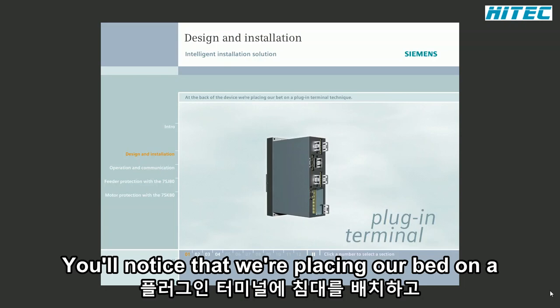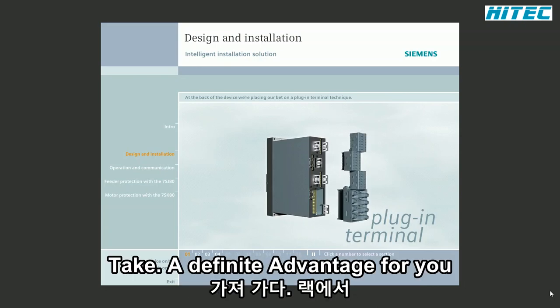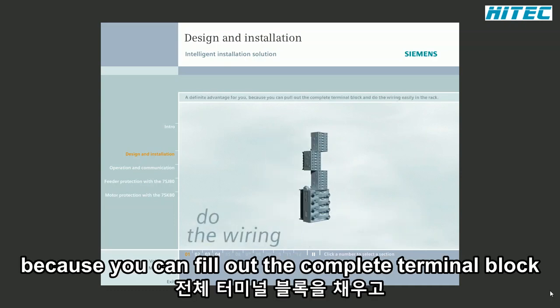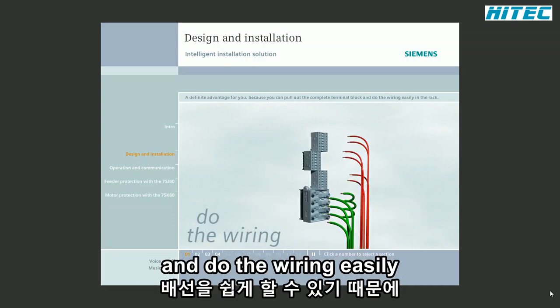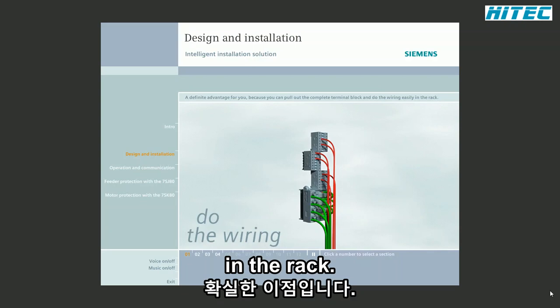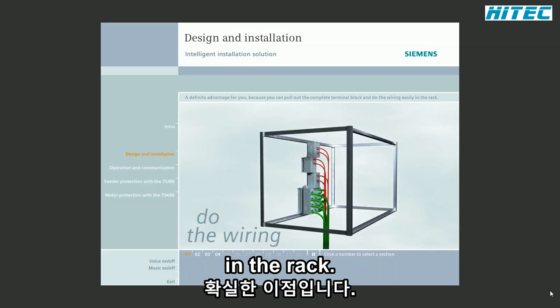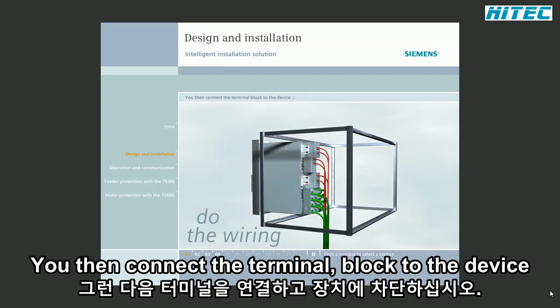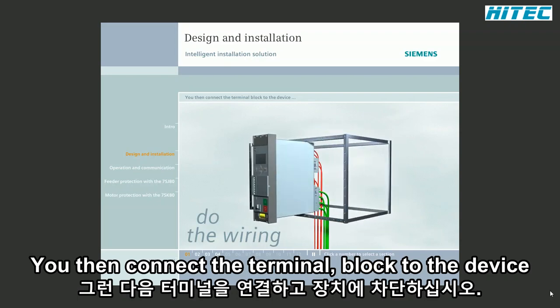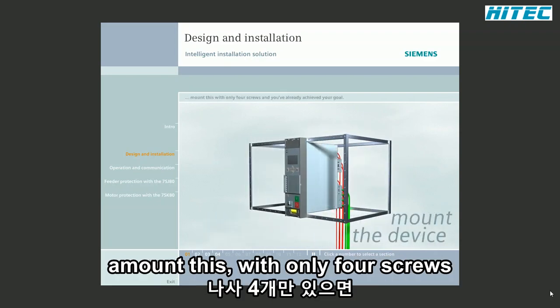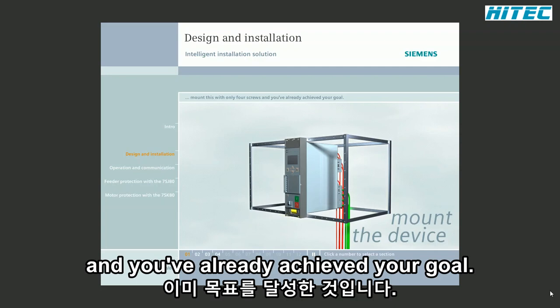You'll notice that we're placing our bet on a plug-in terminal technique. A definite advantage for you because you can pull out the complete terminal block and do the wiring easily in the rack. You then connect the terminal block to the device, mount this with only 4 screws, and you've already achieved your goal.